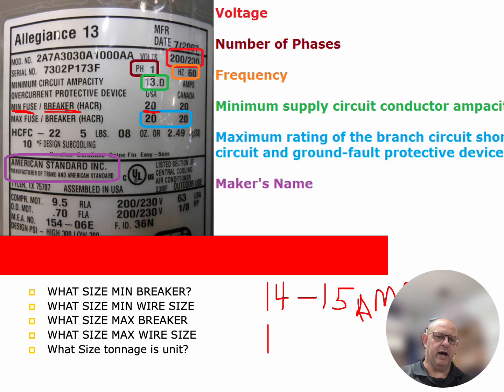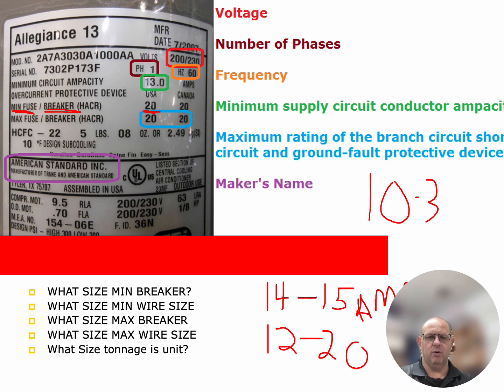The next gauge of wire that we're going to be dealing with is a 12 gauge wire. 12 gauge wire is good for 20 amps. And we're just taking you back to your electrical knowledge in the field. And then for the next size up, we're dealing with a 10 gauge wire. And that 10 gauge wire is good for up to 30 amps. And these are the minimum breakers that you can place on the certain size wire going on this particular unit.